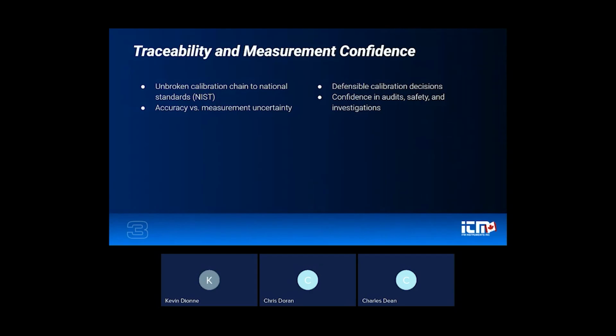There is a distinction between those two. Accuracy tells us how close a measurement is to a true value. Uncertainty tells us how confident we are of that result once we take into consideration all influencing factors. So reference accuracy, resolution, repeatability, environmental conditions, operator technique, all of this is taken into consideration. In a properly traceable calibration, uncertainty isn't ignored or assumed. It's calculated and documented. The end result of traceability is confidence that a pass is truly a pass, that a fail is truly a fail, and that measurement data can stand up during audits, safety reviews, investigations, etc.